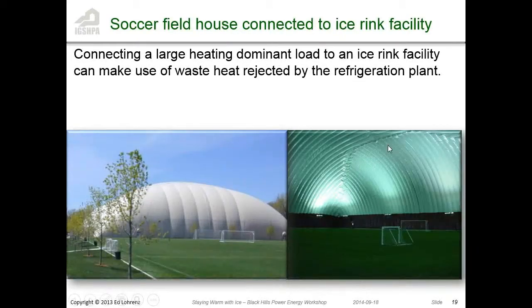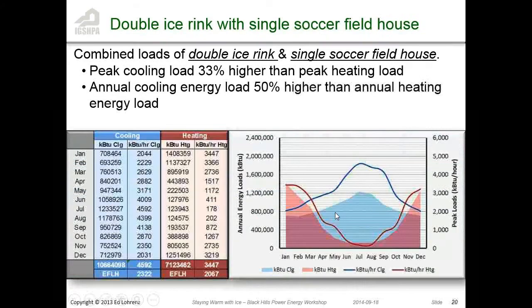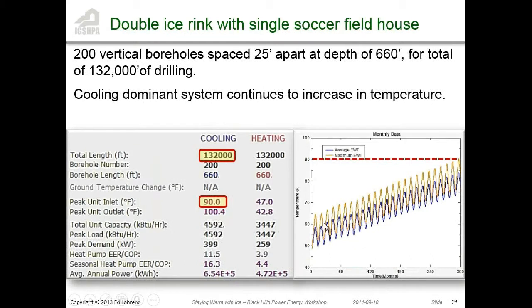So looking at a double ice rink in a single soccer field house, peak cooling loads are still 33% higher than the peak heating loads. And the annual energy loads are still a lot higher than the annual energy heating loads. So what's going to happen then, even with 132,000 feet of drilling, we're going to get a temperature increase over time.